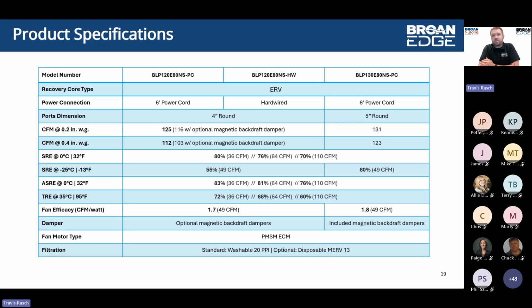The last thing to stress here is the BLP 120 models. If you want dampers, and code likely requires you to have dampers, you can purchase the optional 4-inch kit I'd mentioned earlier. If you're on the BLP 130 model, the unit will come shipped with magnetic backdraft dampers that you can both rotate and pull out if you need. And those are 5-inch in diameter.